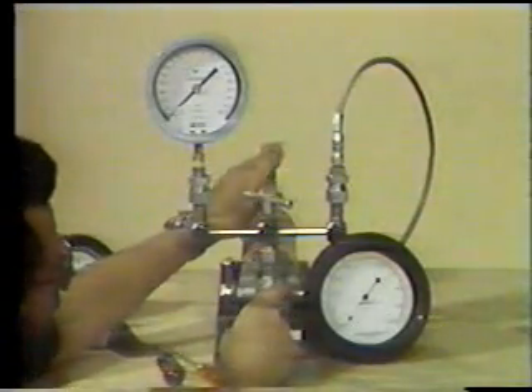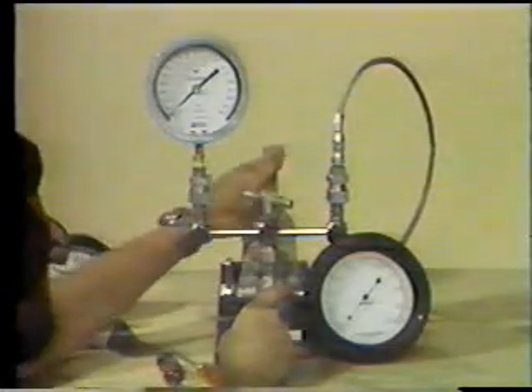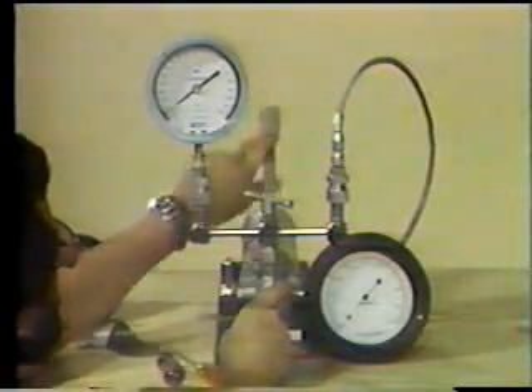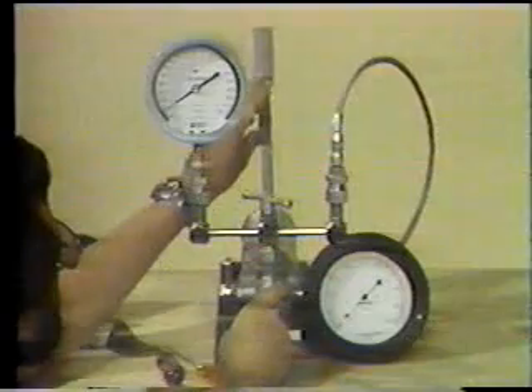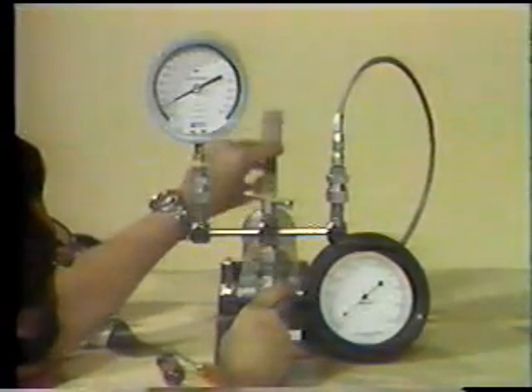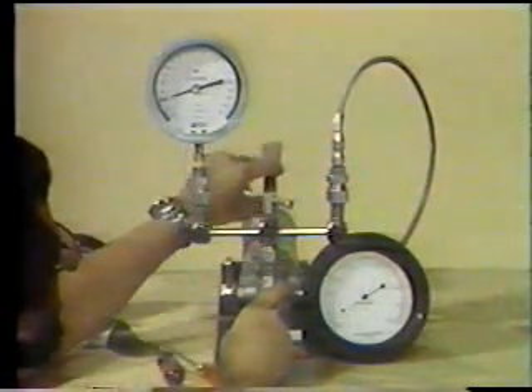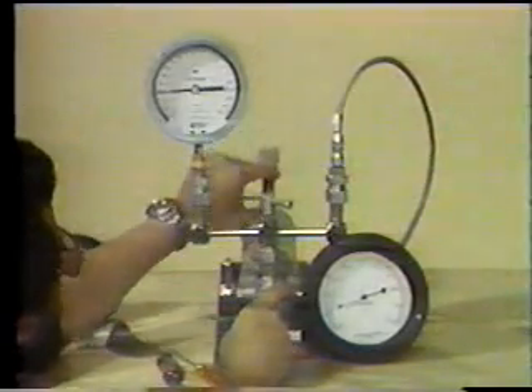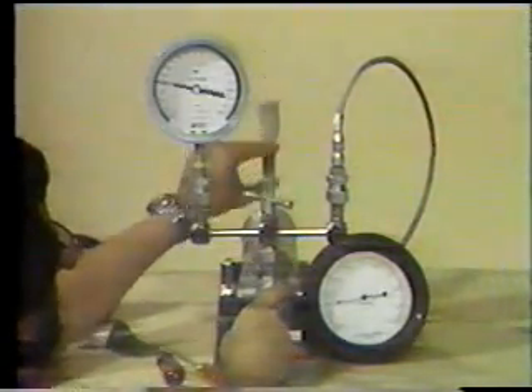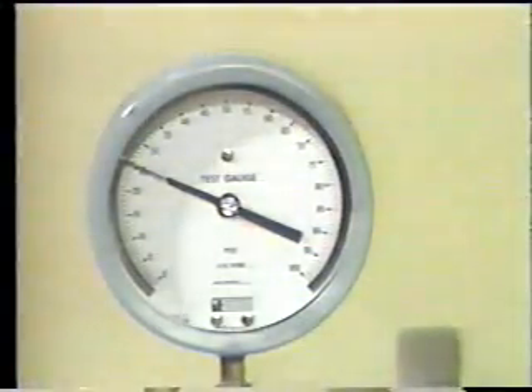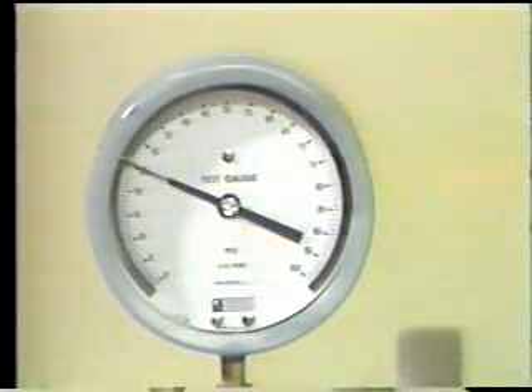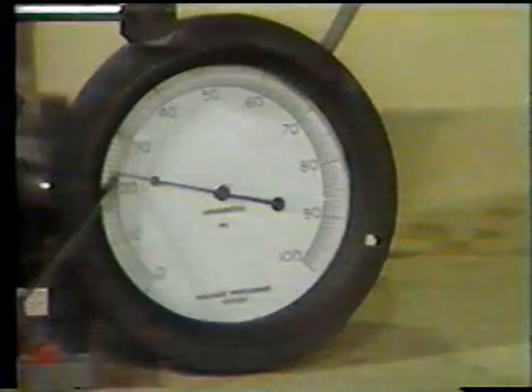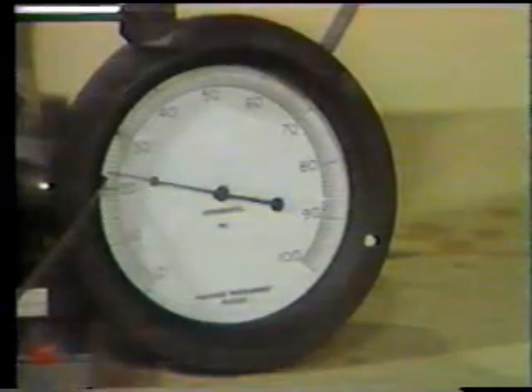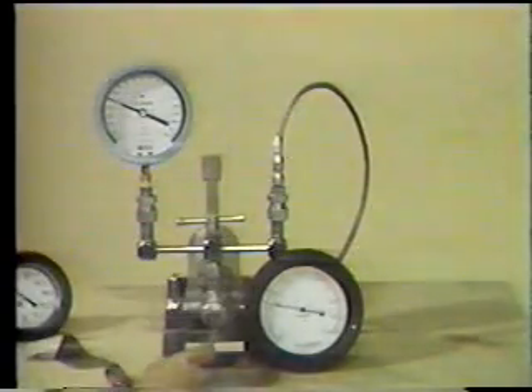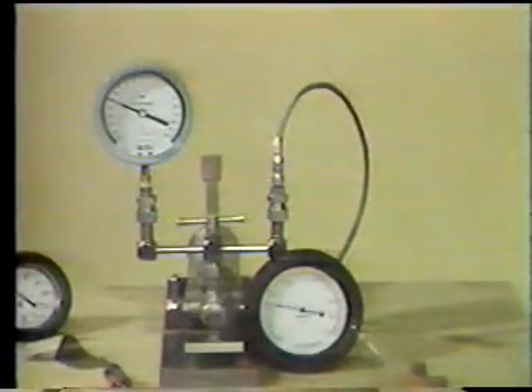Next, position the gauge so that it can be easily read when applying pressure. Then increase pressure to both gauges. In this example, we will use 25 pounds as our calibration point. Once you have reached the correct pressure on the master test gauge, compare the reading to the delta P gauge reading. Any difference in readings indicates an adjustment is required.